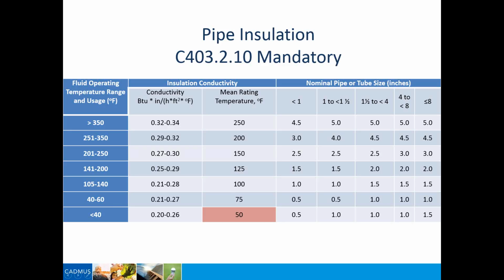That's really kind of considered unconditioned water. I'm not sure how prevalent water source heat pumps are in Hawaii. You're probably not worried about the heating side, but if you did want to use a water source heat pump, a lot of times the water temperature you're getting your cooling from is probably going to be in the 60 to 105 degree temperature range, and those pipes typically aren't insulated.